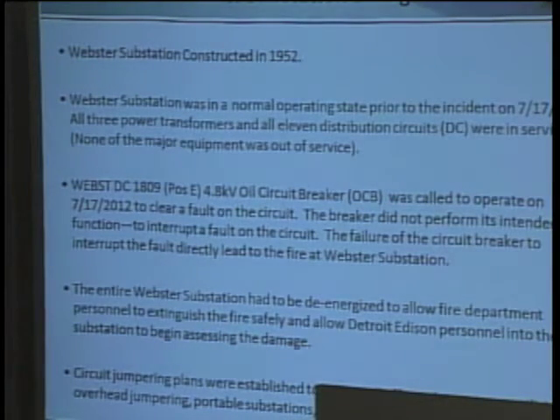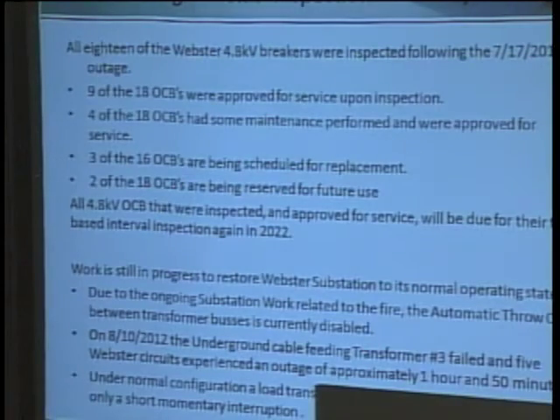There's nothing really burning in the substation except for the cables and the fact that the fault was still energized, so the fault was feeding the fire, which was burning the equipment and some of the metal in this position. Circuit jumpering plans were established, and load where possible was transferred to adjacent substations. In those areas where we couldn't get the jumpering, we had to put in the portable substation and 3 generators located at various areas, and I believe one of them was near here.